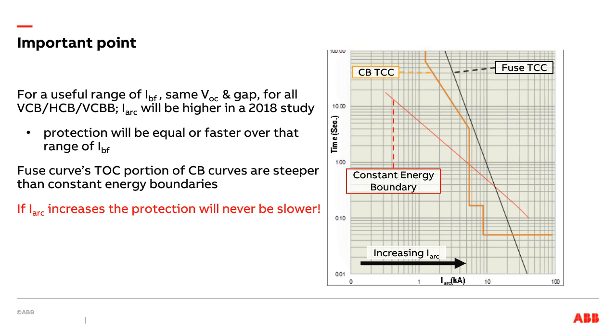And in the old standard, I'm not sure it made that huge a difference. But in the new one, it does make a little bit of a difference. Let me give you an example. The company that I'm most familiar with makes 5 kV and 15 kV switchgear. The reality is that was the same switchgear with a different nameplate. We did not make two different lineups. It was just too cost effective to have two completely different designs, two different sets of bus bars, two different everything. We made one. We changed the bus bars. Obviously, CTs, PTs, and all that was changed according to the voltage. But the sheet metal, the copper bars, were not changed.